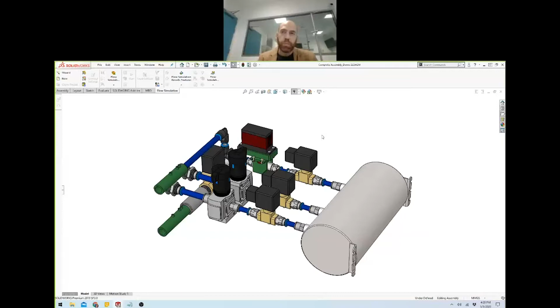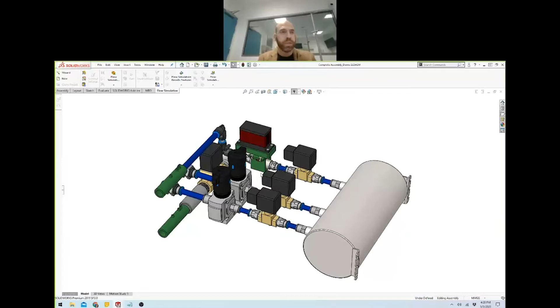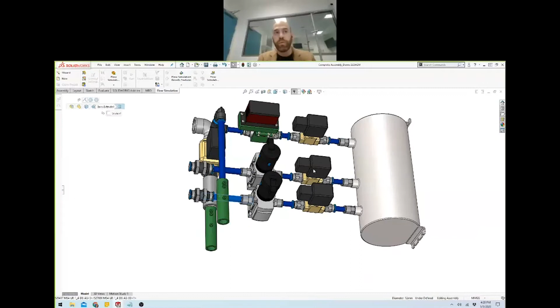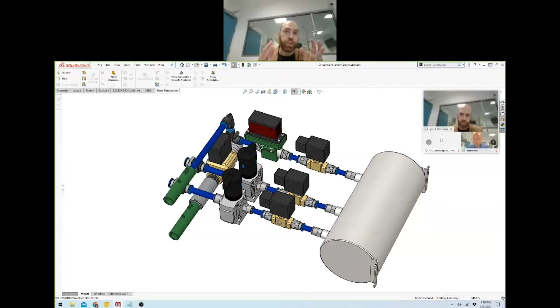In Lebanon, according to the Ministry of Health, there are 1,200 or 1,300 ventilators, of which those that can be used for this particular purpose are around 500, of which 80 to 90 are, to our knowledge, defective and can be repaired. So the total amount of ventilators available in Lebanon is around 400, 410, out of which 200 or so are in usage for non-COVID-19 patients. So that would be people who have the need for ventilators without being COVID-19 patients. So when we looked at these numbers, it was clear from the start that there's going to be a need for ventilators.